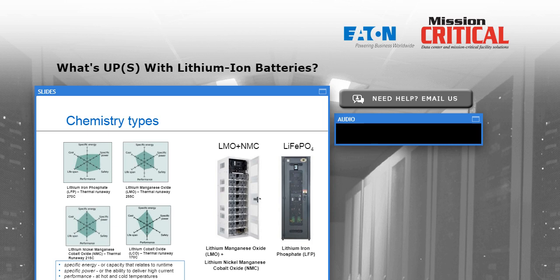The next spider chart shows a lithium manganese oxide chemistry. In the cabinet on the left, the white cabinet, we combined that chemistry with lithium nickel manganese cobalt oxide. That's a lot of chemical names in a row if you're not a chemist. The most important word there is oxide, because that means the battery has the capability to make its own rocket fuel—that's why lithium batteries tend not to burn like campfires, but like rocket engines. So we must be very sure that the batteries are operating safely and we do not get into a mode where thermal runaway could occur.